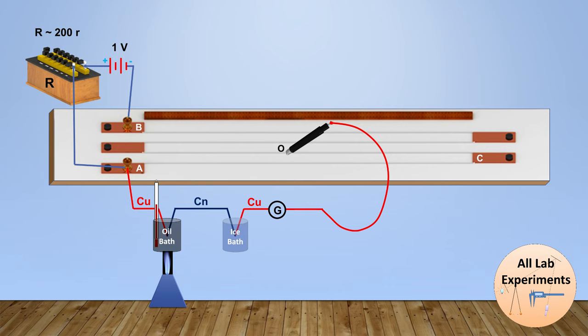The external resistance is so high just because the EMF generated in this thermocouple is of the order of around 40-41 microvolt per degree Celsius. So for each degree Celsius, 40-41 microvolt EMF changes. So the potential drop in this potentiometer wire should be of the same order for this comparison.